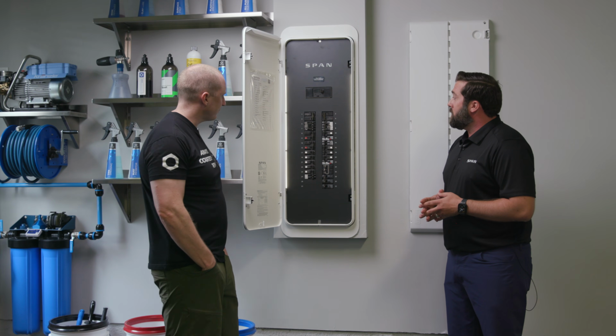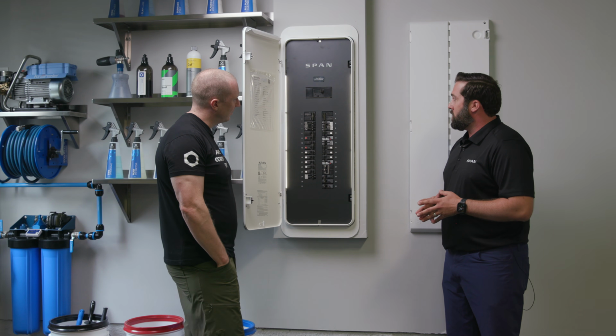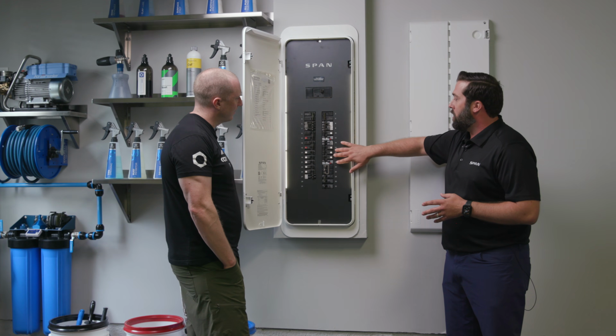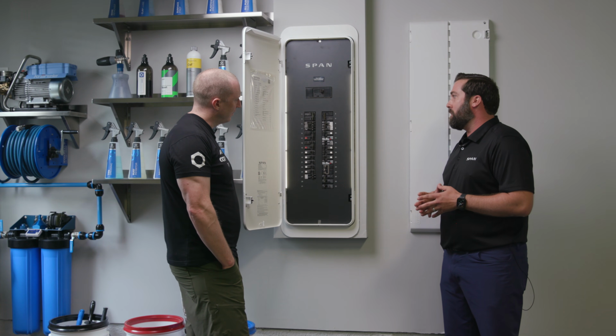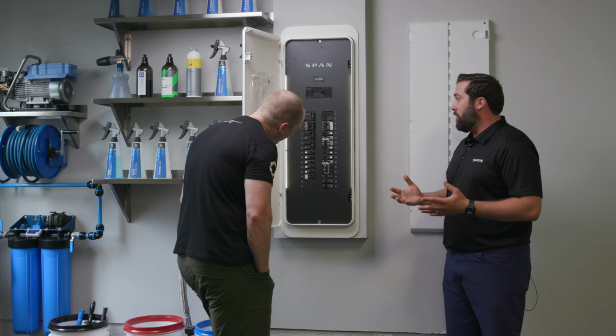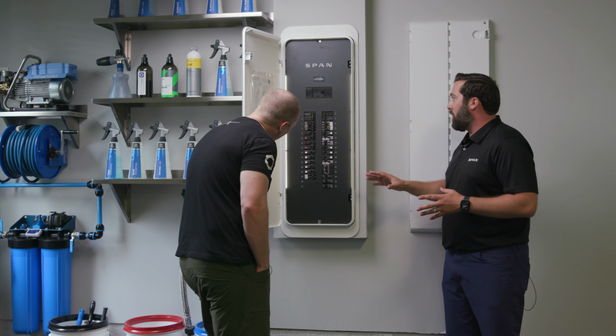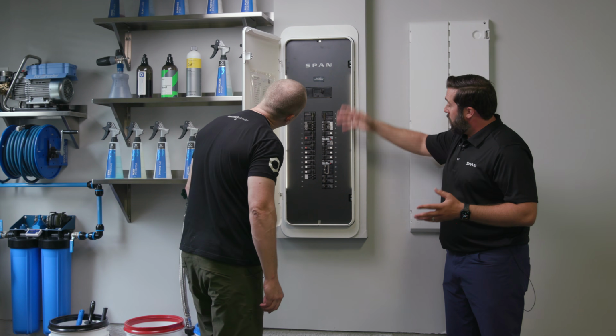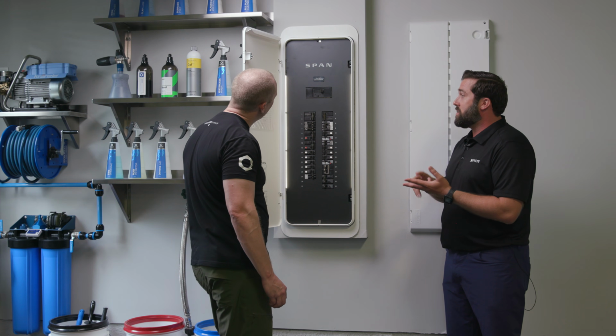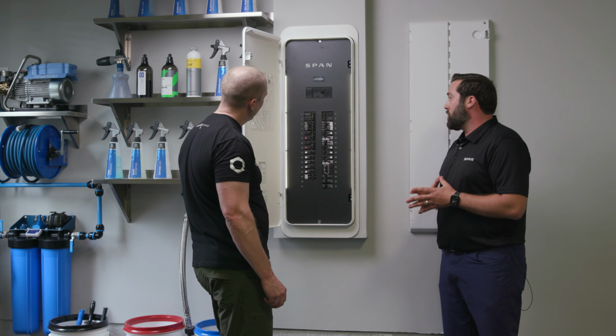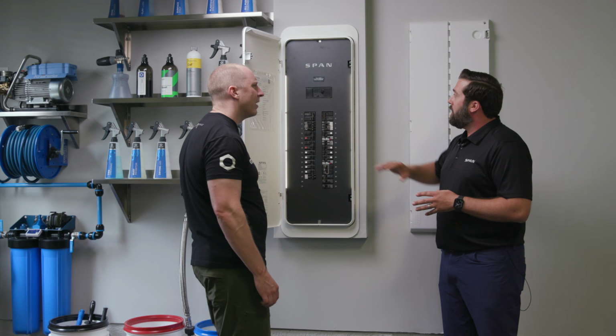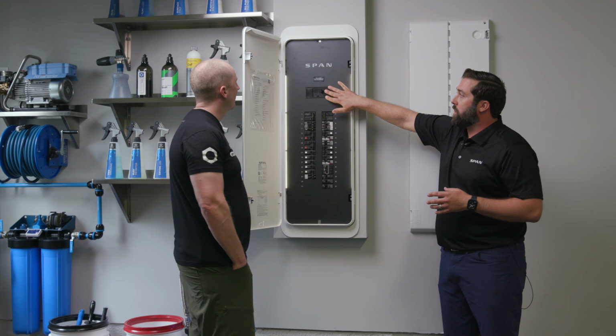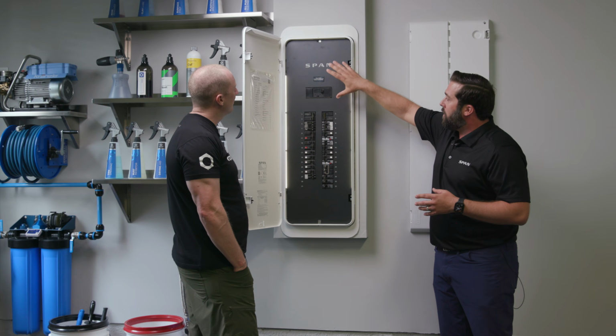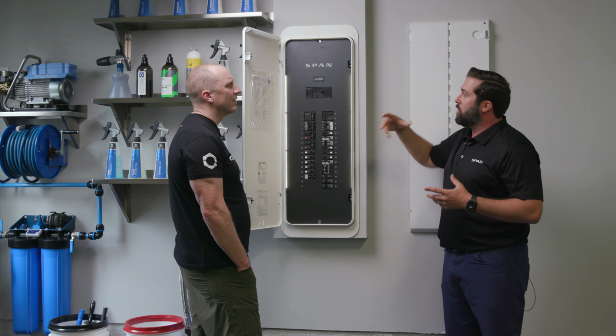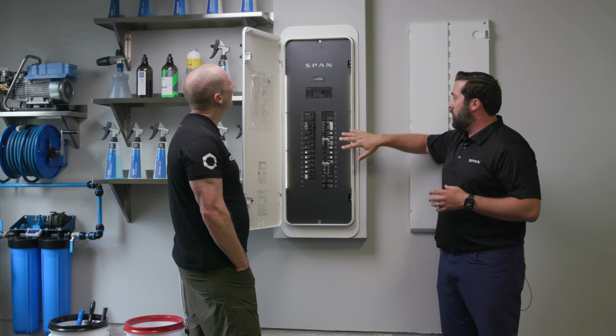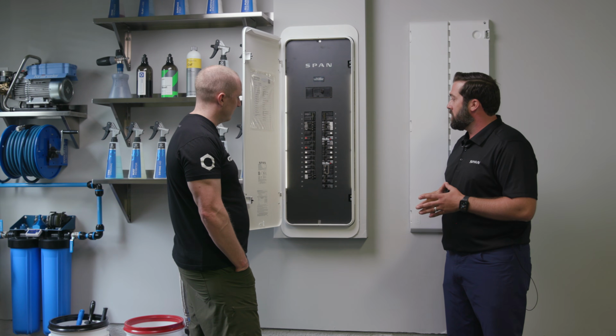That's a unique feature with our panel. Through our certification process, there's a number of standard off-the-shelf breakers that can be used. We do not manufacture breakers, and you don't use smart breakers in our panel. GE, Eaton, Siemens, Square D - there are certain models within all those brands we're compatible with. It comes standard with the 200 amp Square D QO main pre-installed, but all the intelligence is built into our backplate: the computer, the relays, all the monitoring controls. So we use standard off-the-shelf breakers.